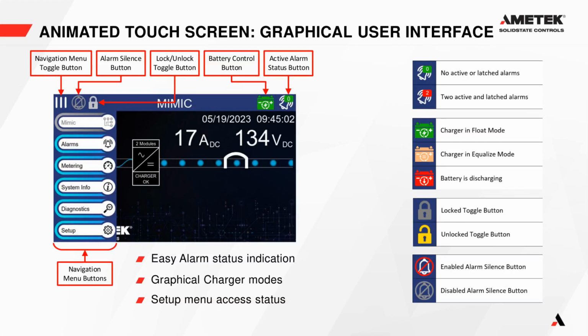The next icon is the battery control icon. Right now it's a green battery to indicate that it's charging, but it also has an equalize mode that is an amber button, and when the battery is discharging, it turns red. If you want to put your system into equalize mode, you press the green battery button. It'll pop up a window that tells you how long you're going to equalize for and at what voltage, and then you can start the equalization from there. And then the last one is our active alarm status button. Like I said, it turns red when there are active alarms, and it shows you the number of alarms. If you press on that button, it'll display a pop-up that shows you exactly which alarms are active or latched.